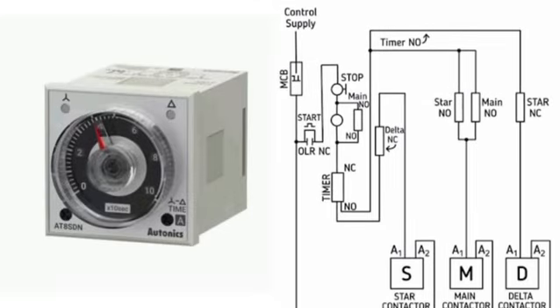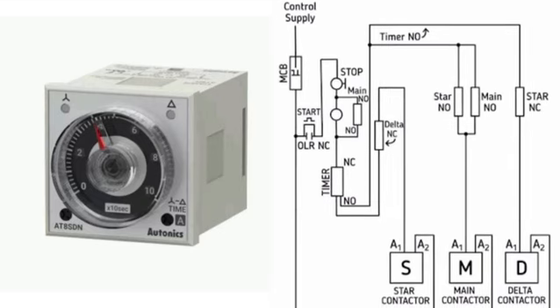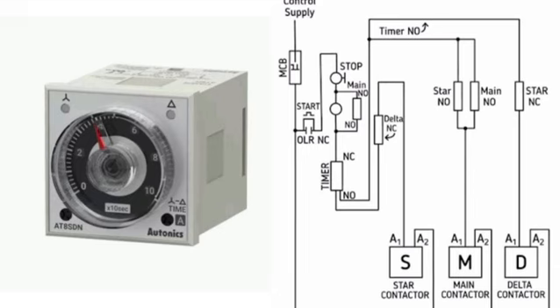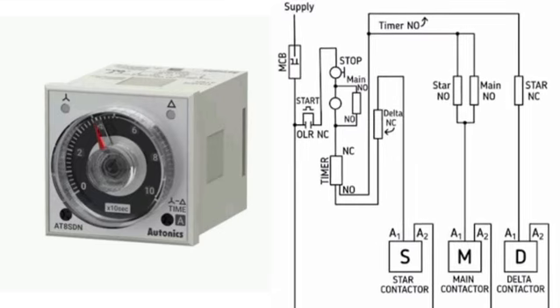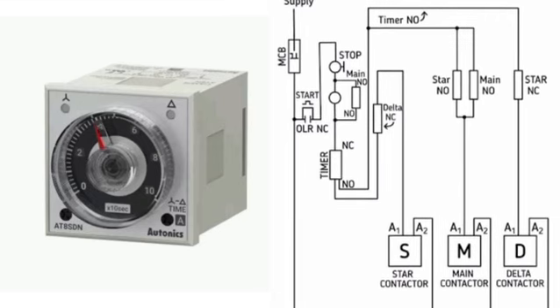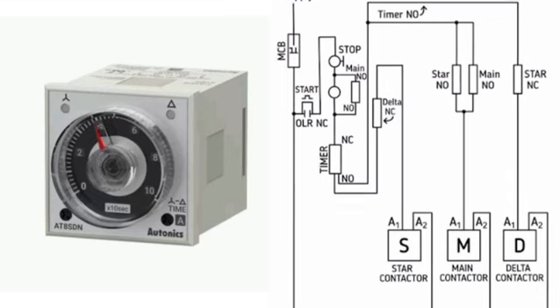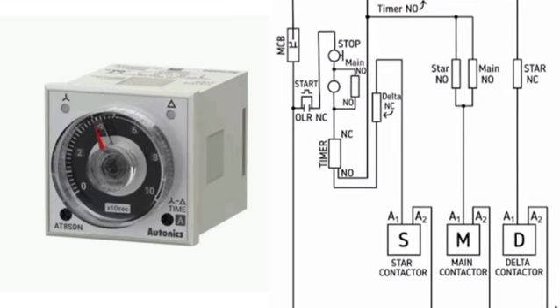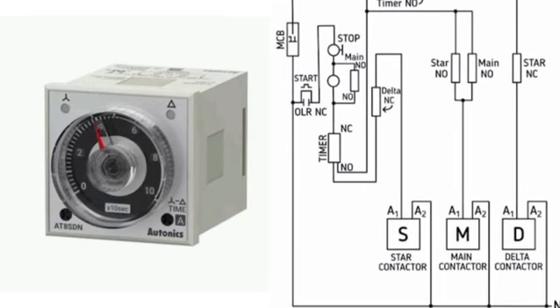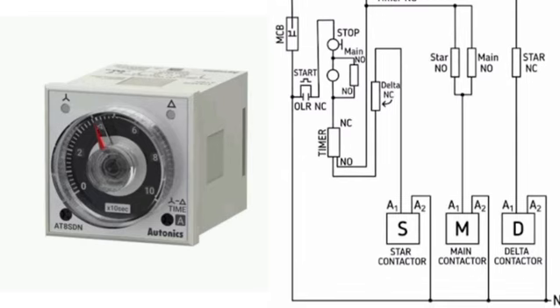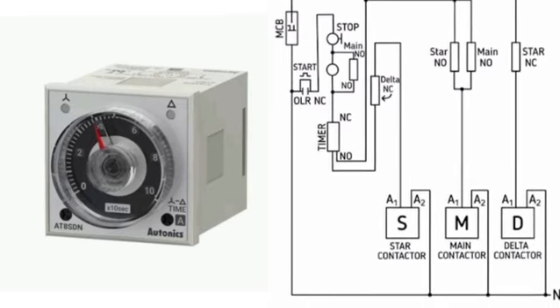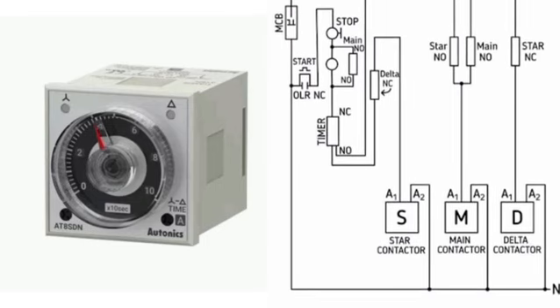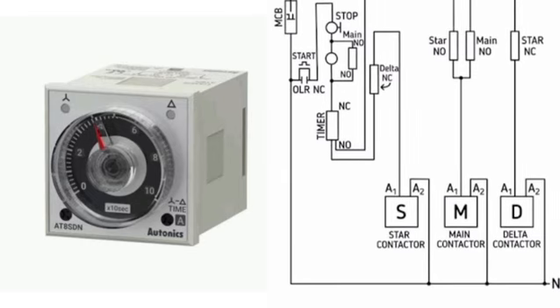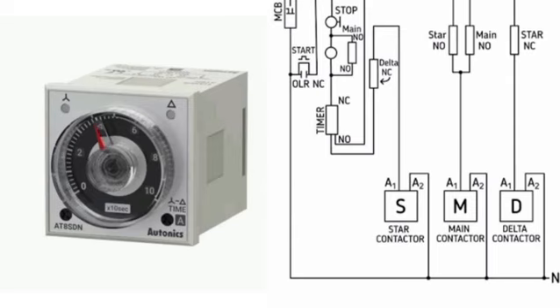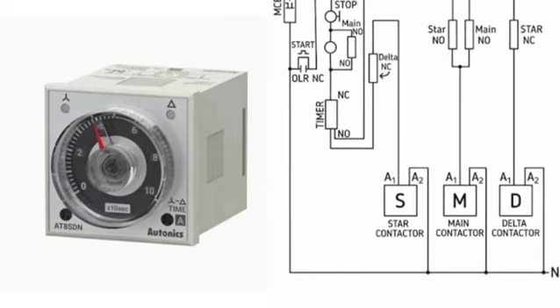Timer-controlled transition. The transition occurs when the motor reaches sufficient speed and torque, usually 50 to 60% of rated torque, often corresponding to a preset time rather than an exact percent, because no speed feedback exists in standard star delta starters. The star contactor disengages and the delta contactor engages. This sequence explains how does a star delta starter work during switching. Proper timing prevents overlap between contactors. The transition must be clean to avoid electrical faults. Automatic switching ensures safe, consistent motor startup without operator intervention.